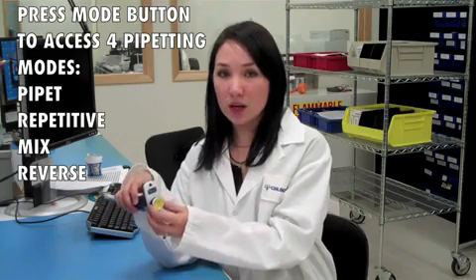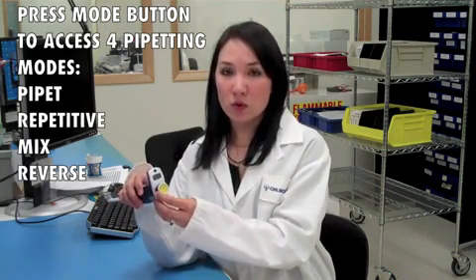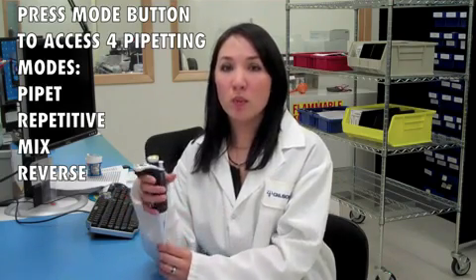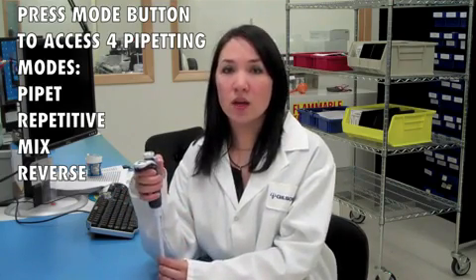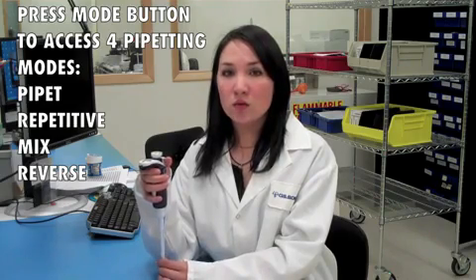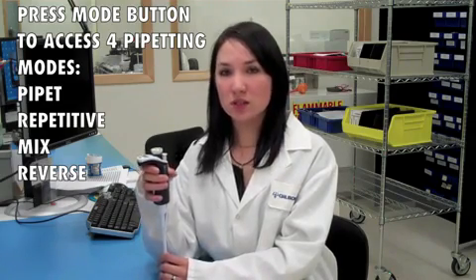It has a repetitive mode, the mix mode, and a reverse mode. The repetitive mode allows you to do multiple dispensing of a set aliquot size. The mix mode allows you to mix two different solutions together. And reverse mode is designed for aspirating slightly viscous solutions.